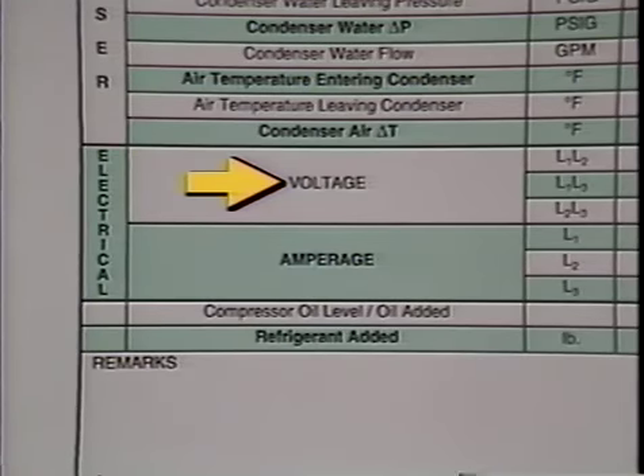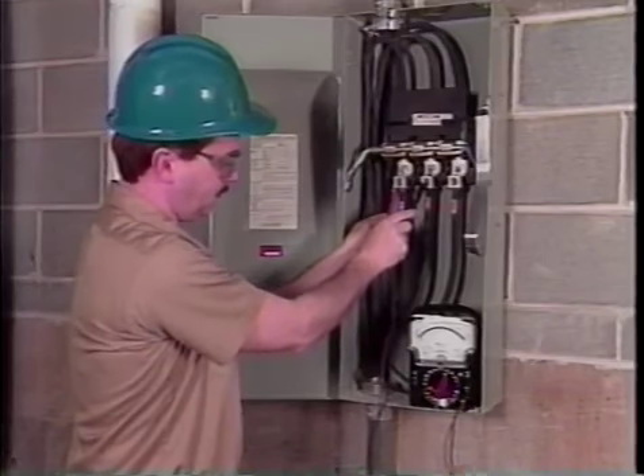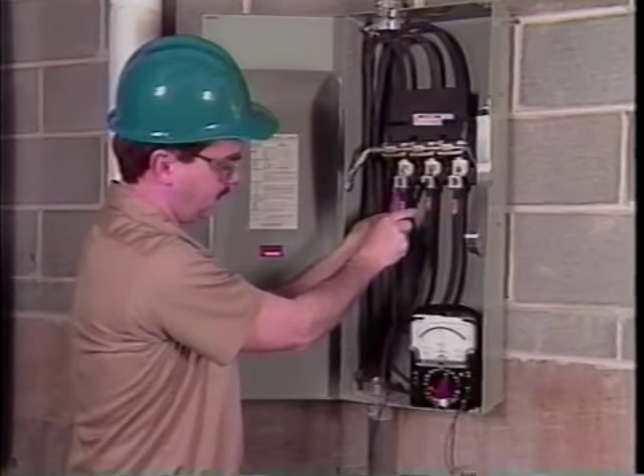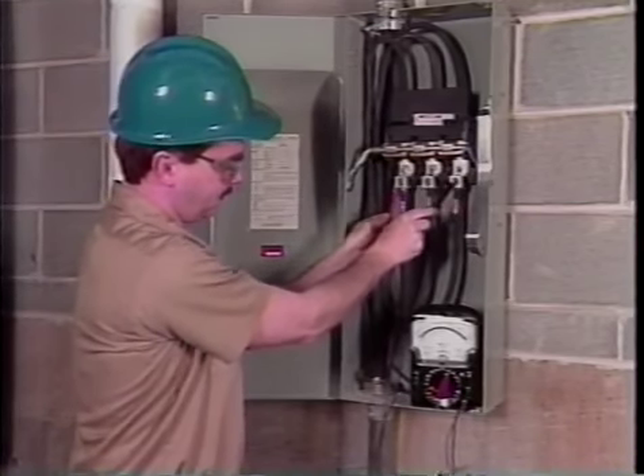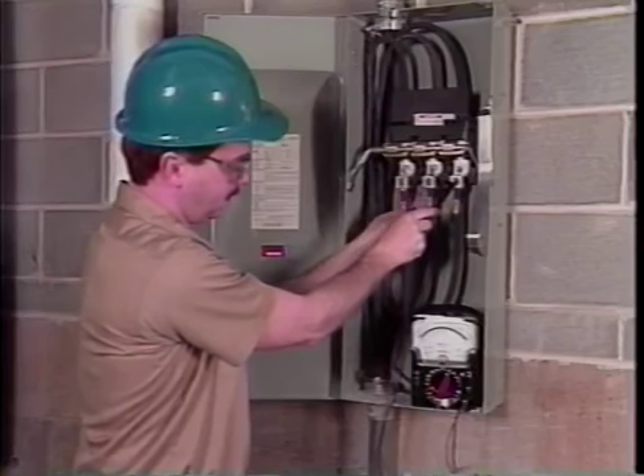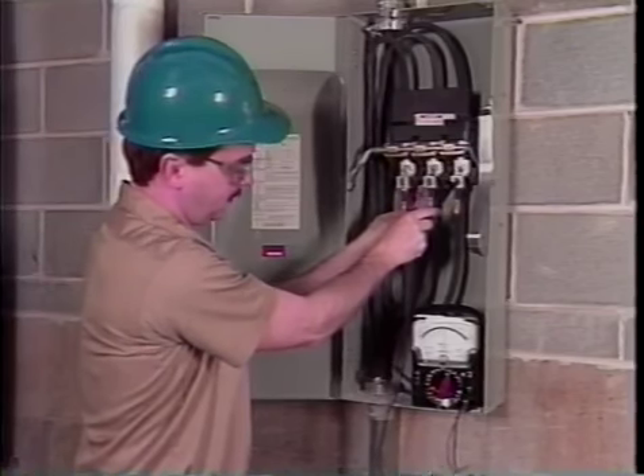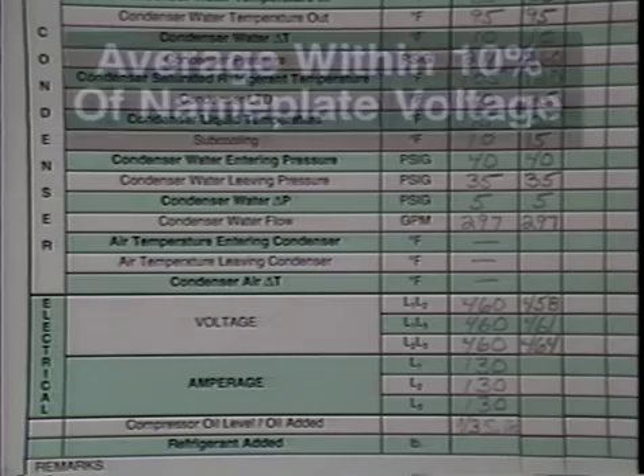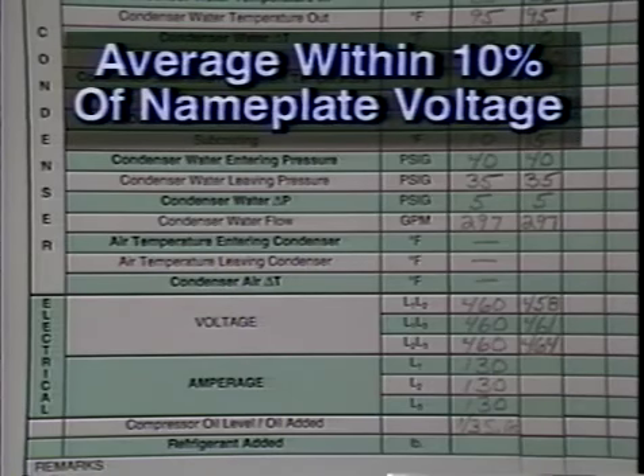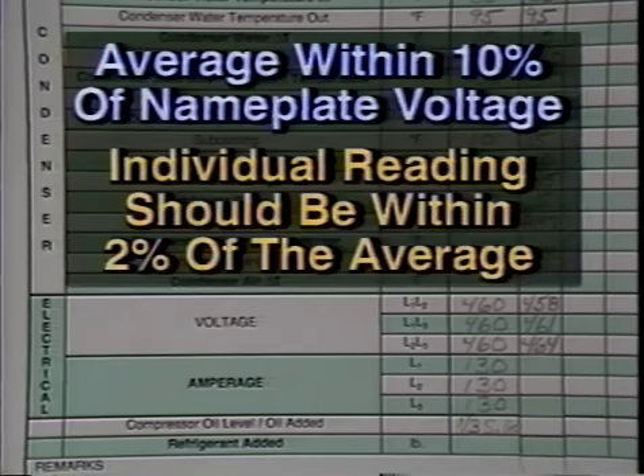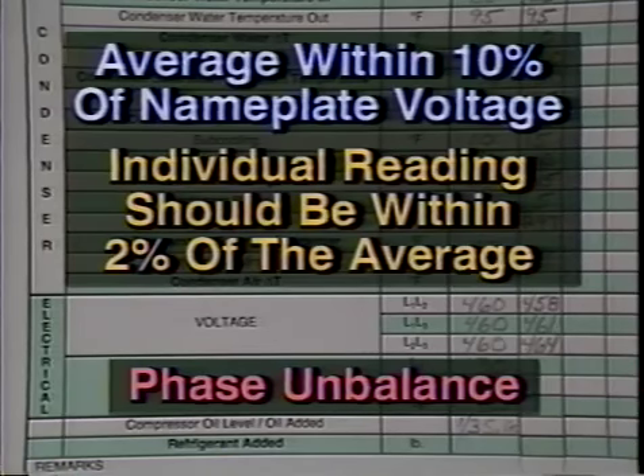Line voltage. Measure the incoming supply voltage and record each leg-to-leg voltage, 3 readings. Add the readings and divide by 3 to get an average. The average should be within 10% of the chiller nameplate voltage rating. If any one line voltage reading is more than 2% from the average, then contact the electric utility for correction. This condition is called phase unbalance, and it should never be greater than 2%.